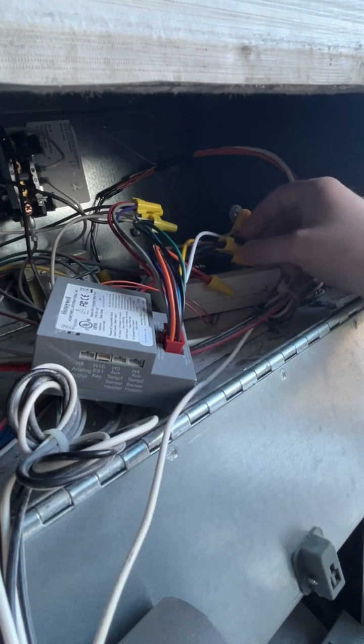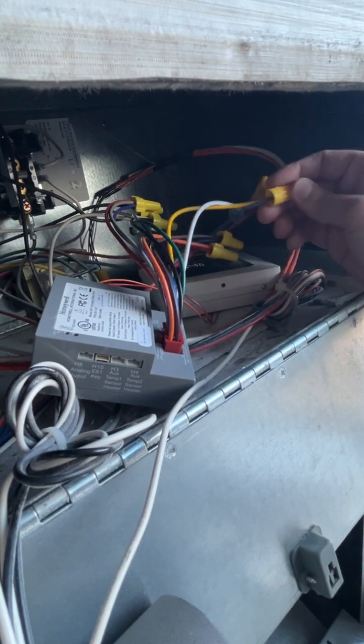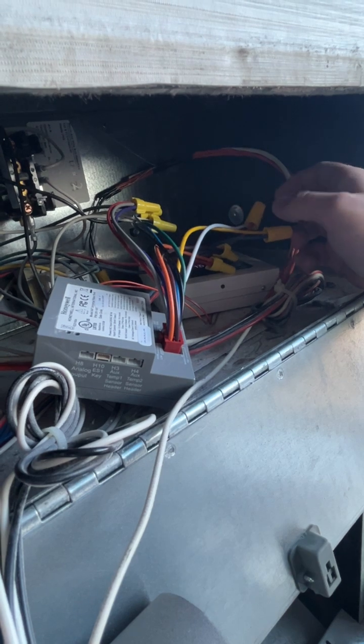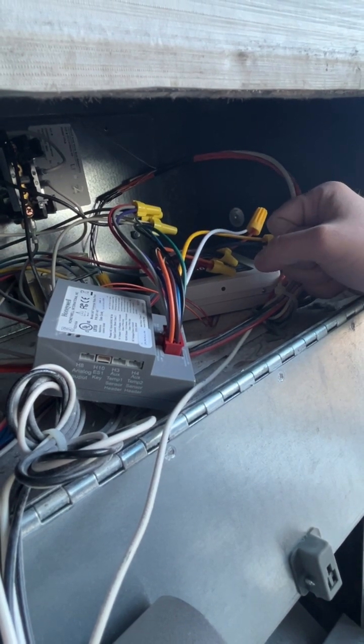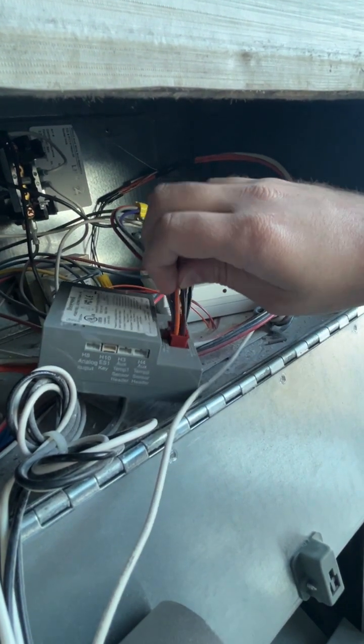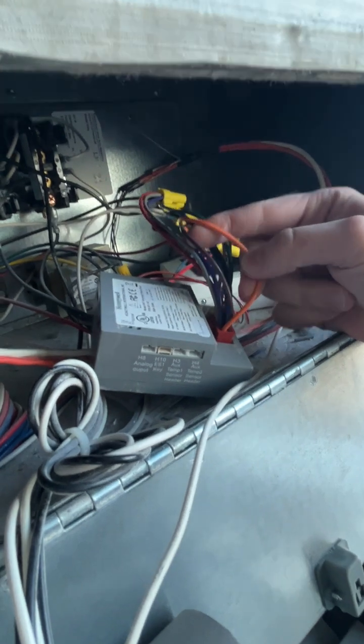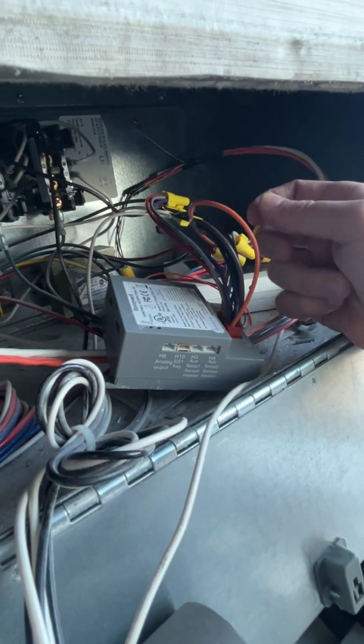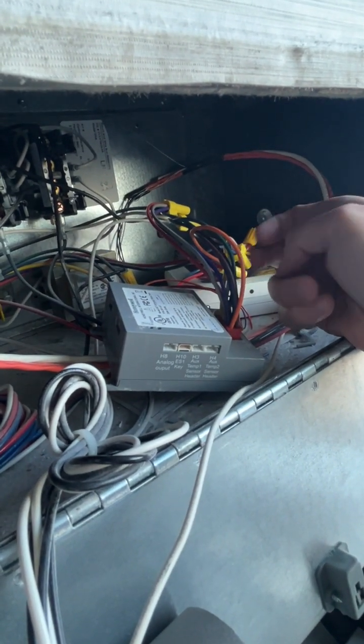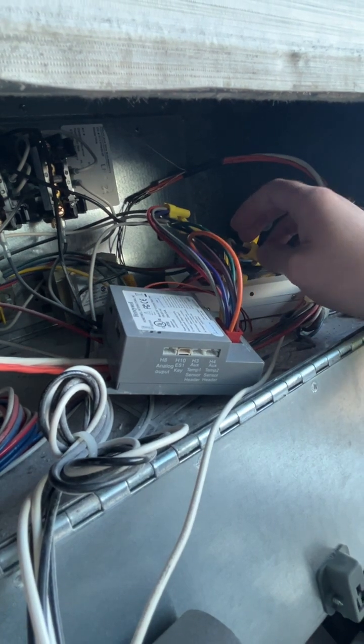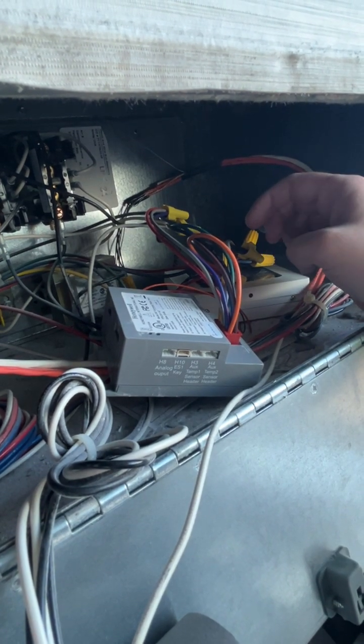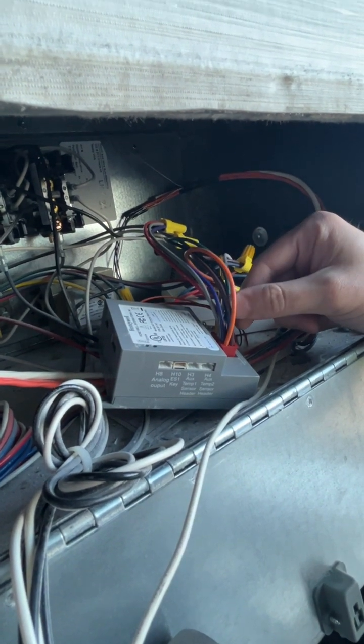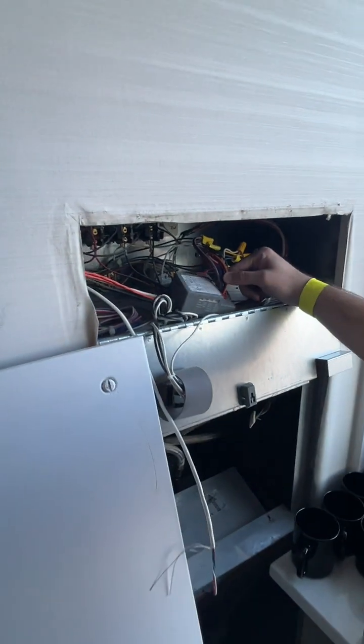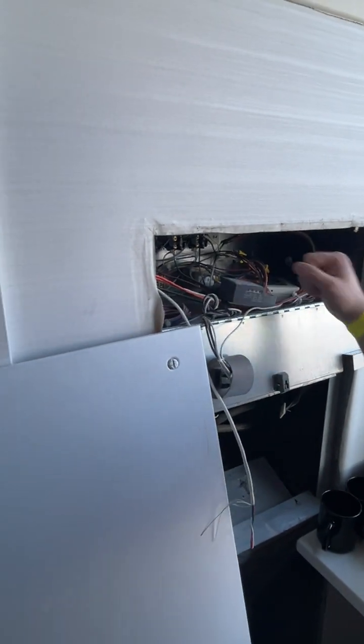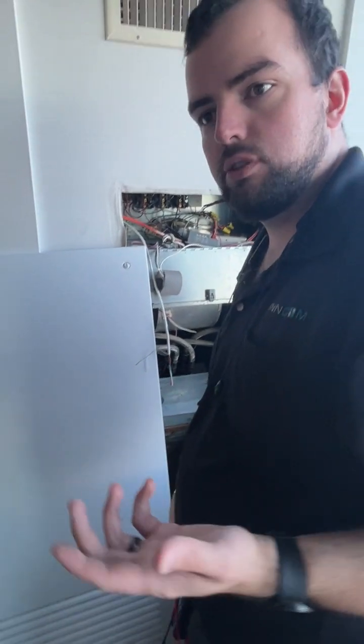If you're trying to check cool, you take your red probe and put it on the yellow wire. If you're trying to test your fan speeds, set the thermostat to low and check your orange, set the thermostat to medium and check your brown, or set the thermostat to high and check your blue wire. Any questions?